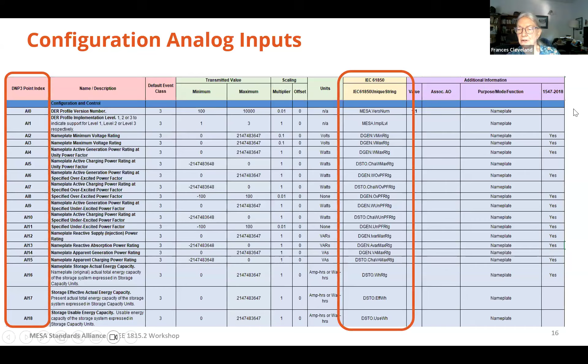This is the same for analog inputs — the DNP3 point with analog inputs 0, 1, 2, 3 and so forth, and the 61850 names. We also have additional information like the scaling factor, as well as the maximum and minimum of a transmitted value so you can do error checking, plus whether it is required by 1547.